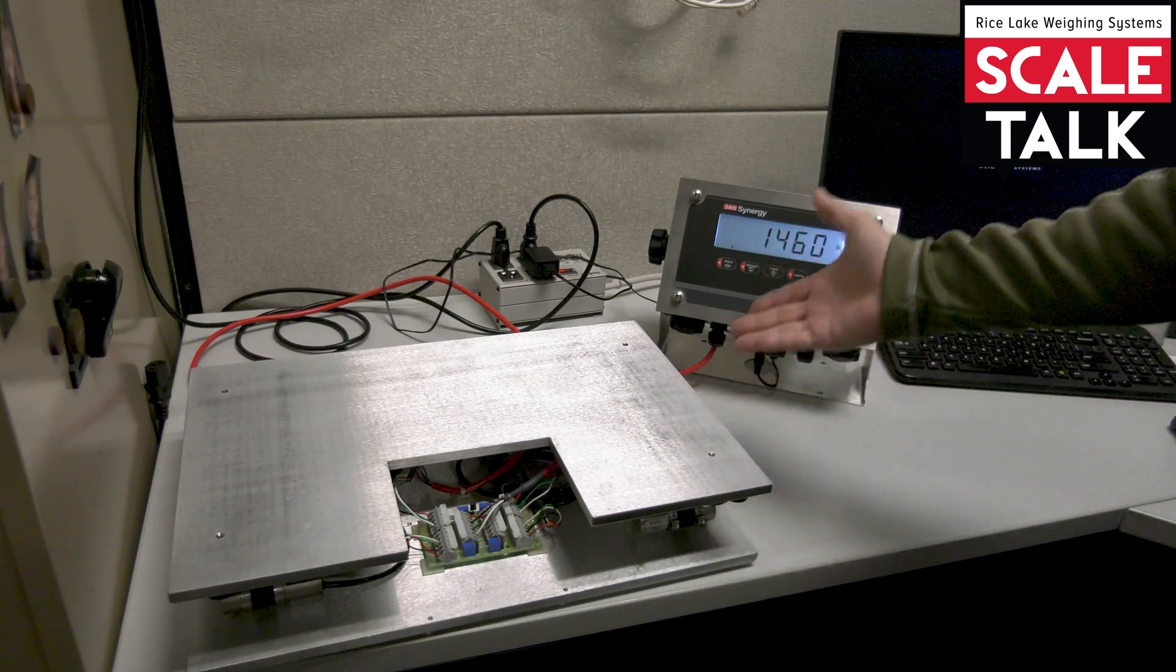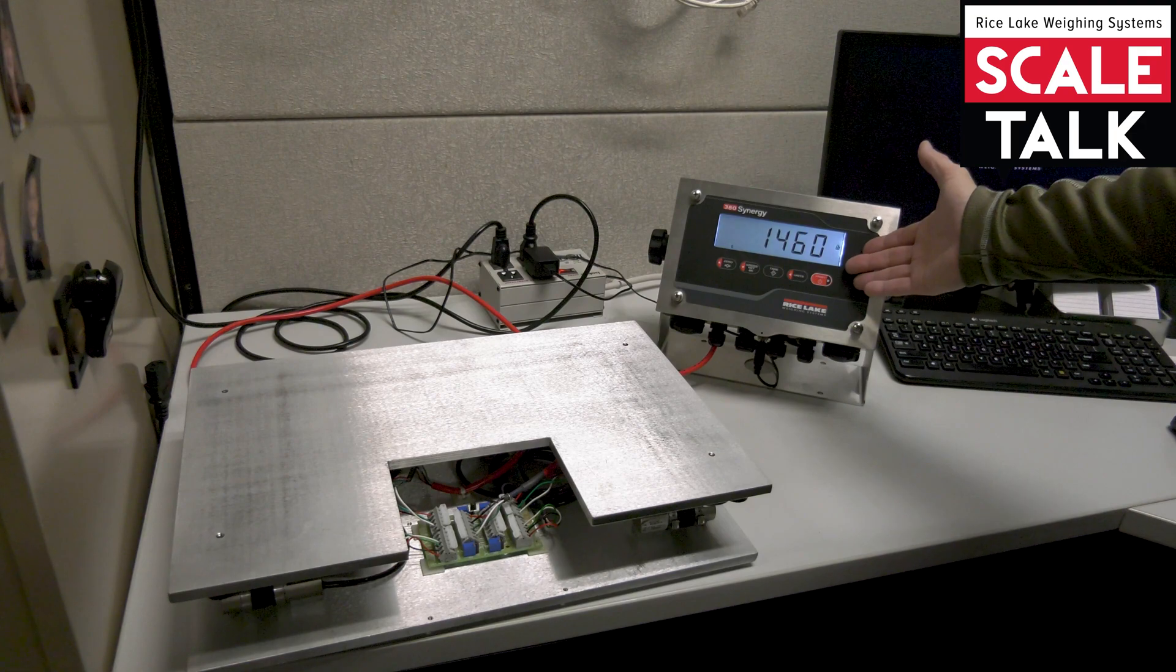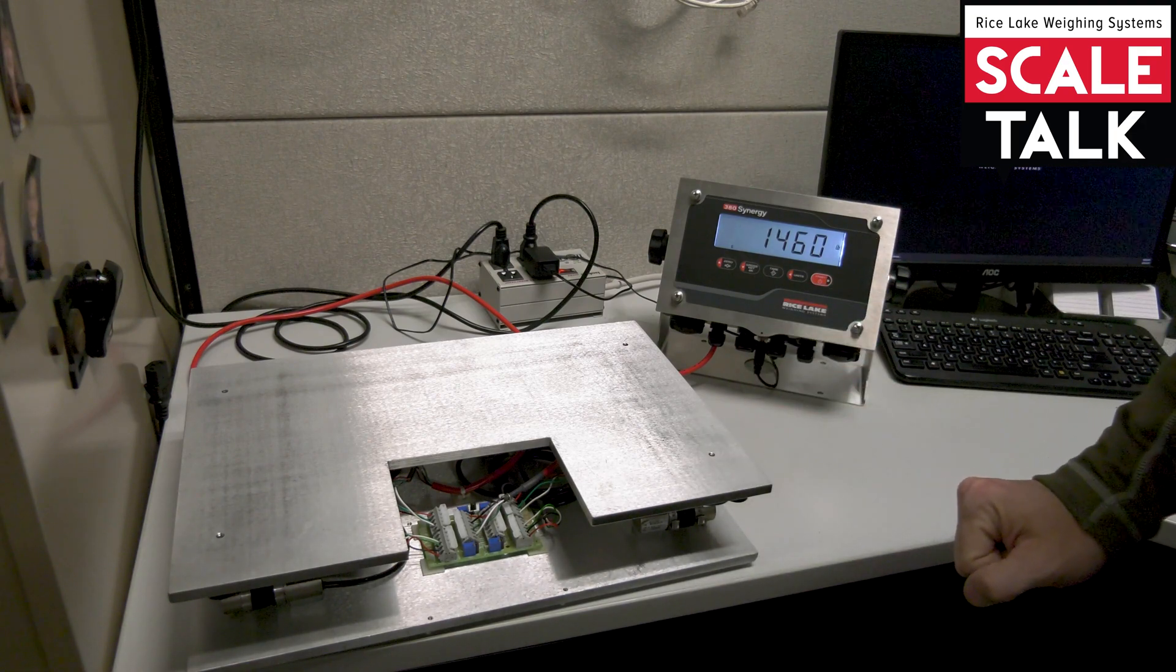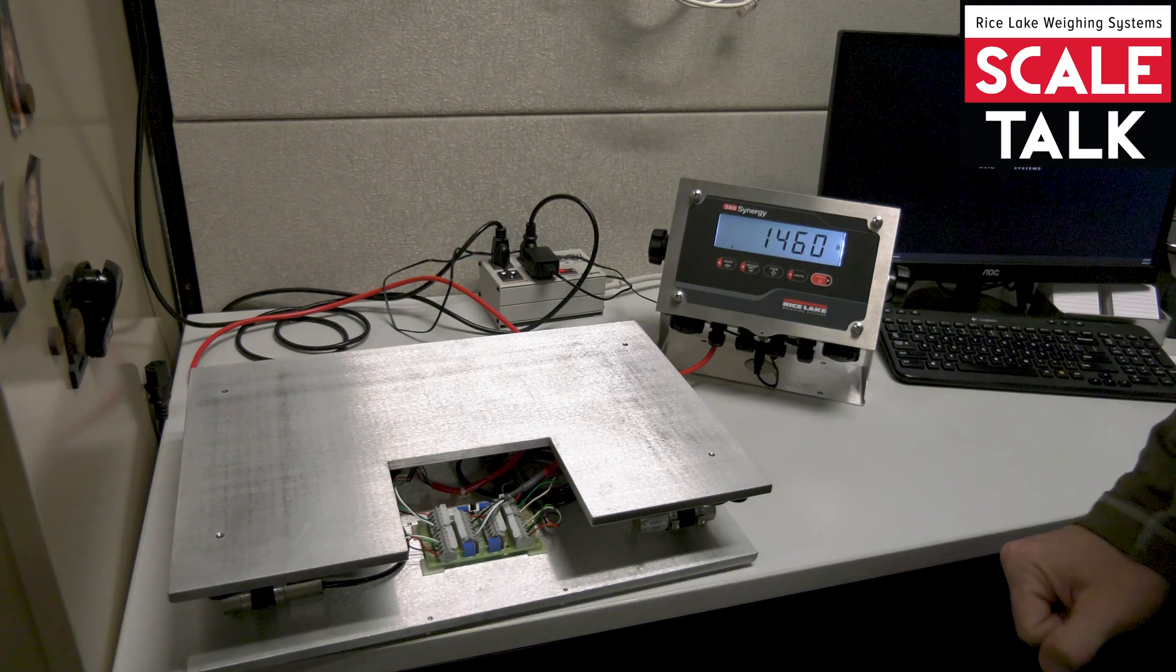Now there's no weight on the scale at the moment and our display reads 1460 pounds, so clearly this is not properly set up or calibrated. So let's go ahead and do that.